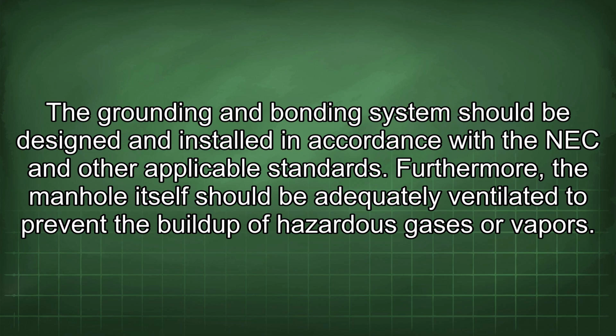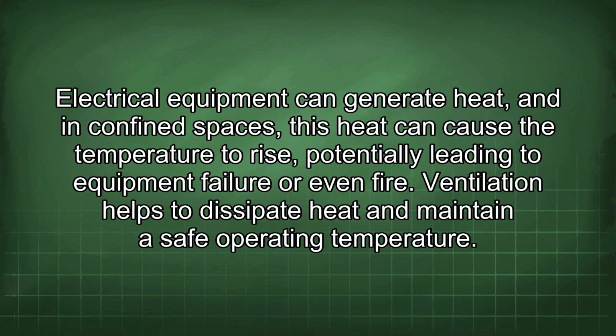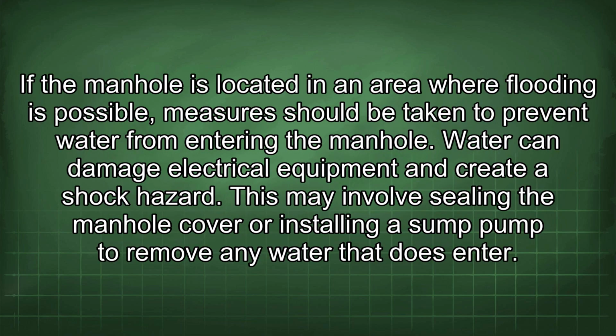Furthermore, the manhole itself should be adequately ventilated to prevent the buildup of hazardous gases or vapors. Electrical equipment can generate heat, and in confined spaces, this heat can cause the temperature to rise, potentially leading to equipment failure or even fire. Ventilation helps to dissipate heat and maintain a safe operating temperature. If the manhole is located in an area where flooding is possible, measures should be taken to prevent water from entering the manhole. Water can damage electrical equipment and create a shock hazard. This may involve sealing the manhole cover or installing a sump pump to remove any water that does enter.